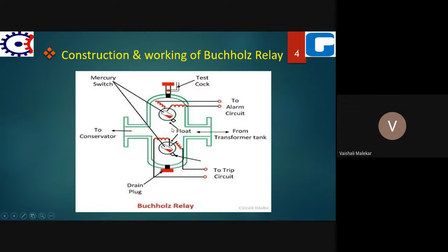Here you can see two hinged floats, one at the top and another at the lower side. So there are two hinged floats, one at the top of the chamber and the other at the bottom of the chamber, and each hinged float is accompanied by a mercury switch. You can see a mercury switch at the top side and also at the lower side, along with the hinged float. The mercury switch on the upper float is connected to the external alarm circuit.